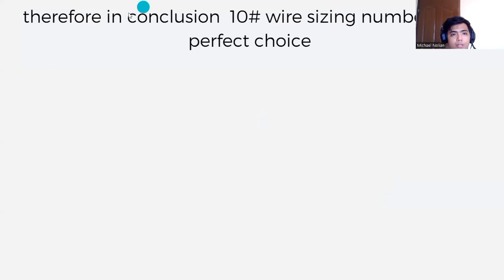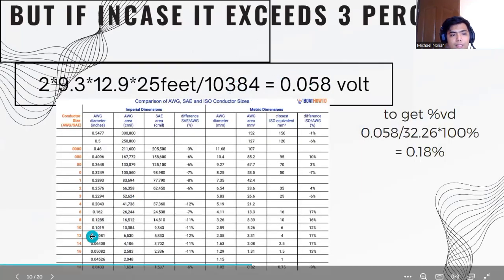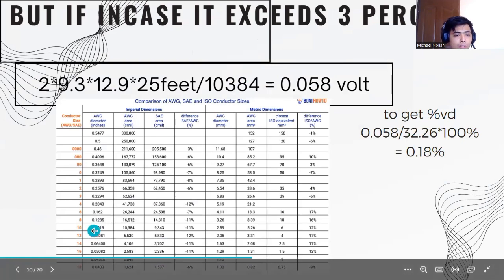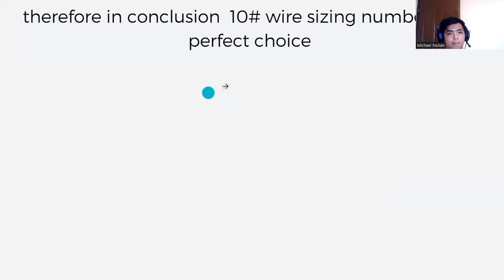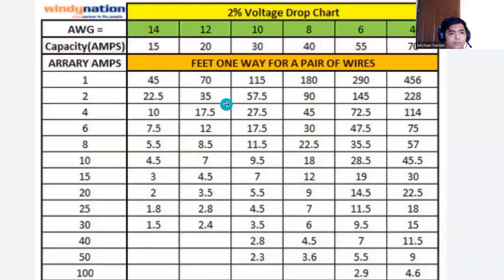So the perfect choice, we just test it: if the sizing is 10, I remember, it's 10. With this sizing of 10, this number, 0.18, does not exceed the limit. Therefore, in conclusion, the number 10 wire sizing is the perfect choice. So what is this table? It went over.